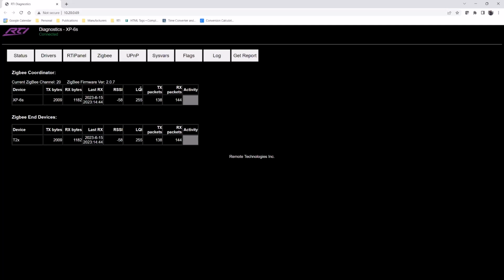If you're a little bit lower, like 180, 190, it might be okay. But try to get into that 200 to 255 range, which means that you may have to put in an extender, you may have to put it closer, you may have to change the placement, or you may have to take into account any sort of interference areas. But that 200 to 255 is going to be a good all-around range to be in. As I mentioned before, the LQI and the RSSI are both found on the counter driver page on the remote. I'll show you where that is here in just a second, and I've got a little hint for you on that as well.